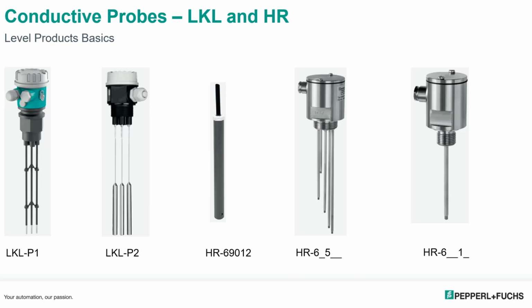The family of conductive probes, the first ones we have are the LKL-P1s and P2s. This is like a plastic housing. This is the most common, less expensive unit that we have. The P1s indicate the rod version, the P2 indicates the cable version. P1's maximum length is about 2 meters. The P2s, you can get up to about 30 meters, 20 meters. I think it's about 25 meters.